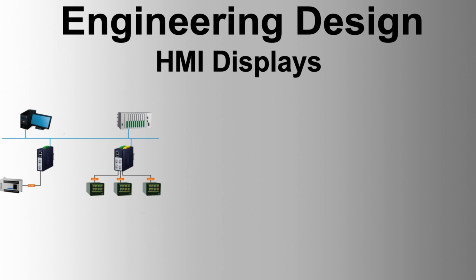Operations and configuration teams should review standard displays early in the HMI design process to determine their fit within the overall HMI design philosophy. Standard displays typically include control group, which displays an array of instrument faceplates corresponding to function blocks in the control station. It allows simultaneous monitoring and manipulation of process variables, PV, set points, SP, outputs, and modes, auto, manual, cascade, for groups of instruments. Each display can show up to 8 faceplates, identified by a page number or a user-assignable name.